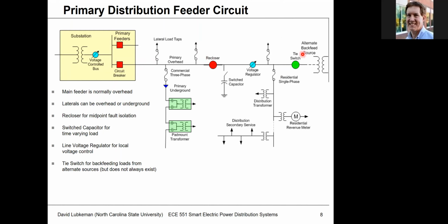Then you get outside the fence, kind of at the street level. Usually it's overhead as far as the main part of the feeder, sometimes referred to as the backbone. When you connect to loads, you run taps off this main feeder, often called laterals or taps. A lot of times it's single phase, but it could be two-phase or three-phase, and these taps are typically fused. They could be overhead, or they can go underground, feeding transformers through cables.